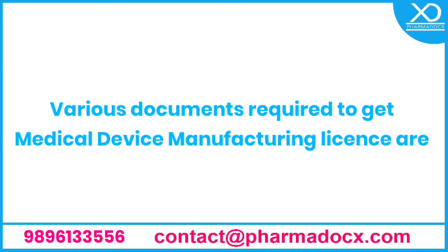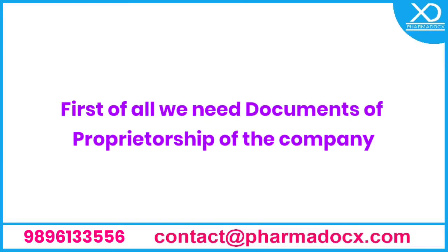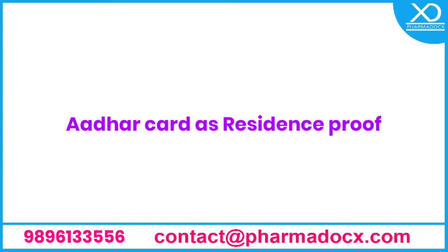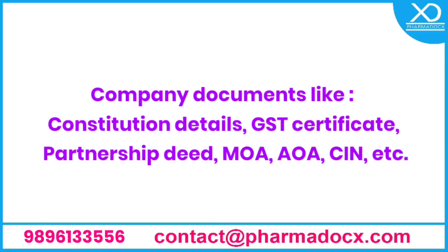Now let us discuss what are the various documents required for getting a medical device manufacturing license. First of all, we need documents of the proprietor or owners or directors of the company. Aadhar card as a residence proof is required. Then company documents like constitution details, GST certificates or partnership deed or MOA, AOA, CIN, etc. are required.